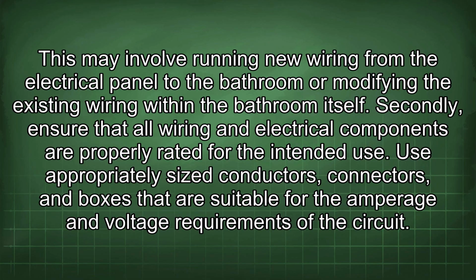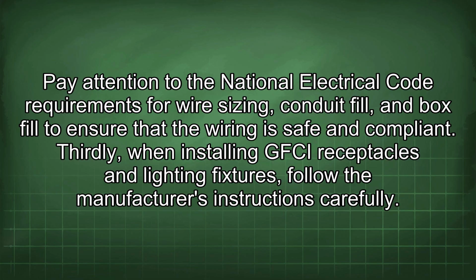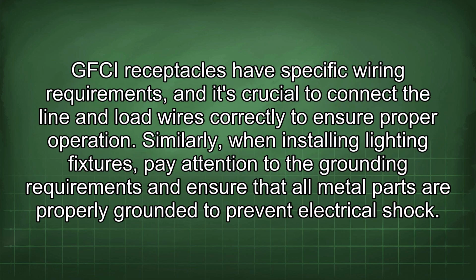Secondly, ensure that all wiring and electrical components are properly rated for the intended use. Use appropriately sized conductors, connectors, and boxes that are suitable for the amperage and voltage requirements of the circuit. Pay attention to the National Electrical Code requirements for wire sizing, conduit fill, and box fill to ensure that the wiring is safe and compliant. Thirdly, when installing GFCI receptacles and lighting fixtures, follow the manufacturer's instructions carefully. GFCI receptacles have specific wiring requirements, and it's crucial to connect the line and load wires correctly to ensure proper operation. Similarly, when installing lighting fixtures, pay attention to the grounding requirements and ensure that all metal parts are properly grounded to prevent electrical shock.